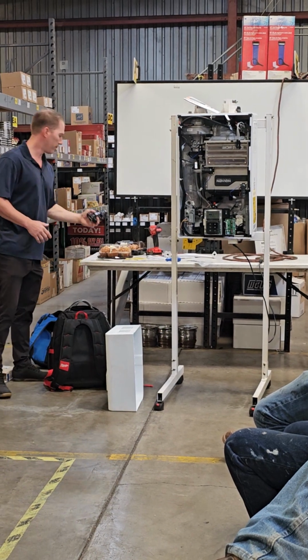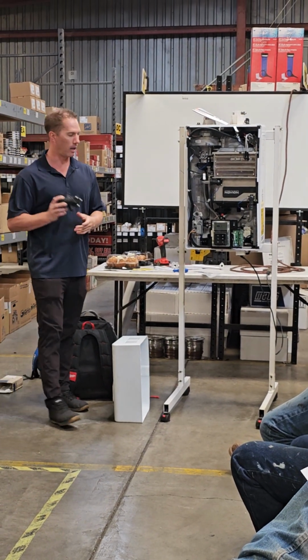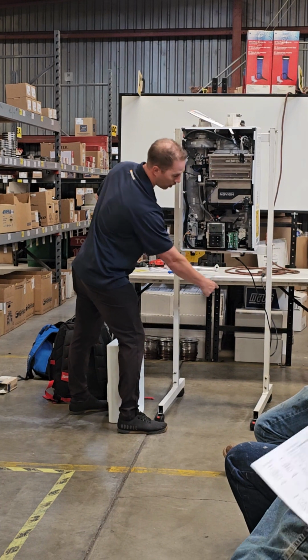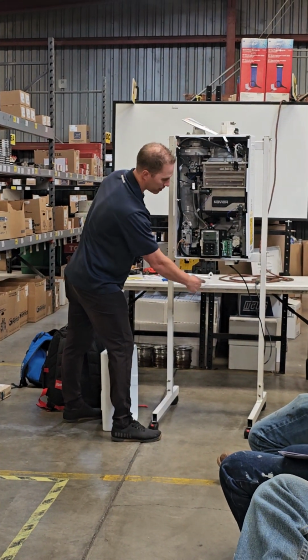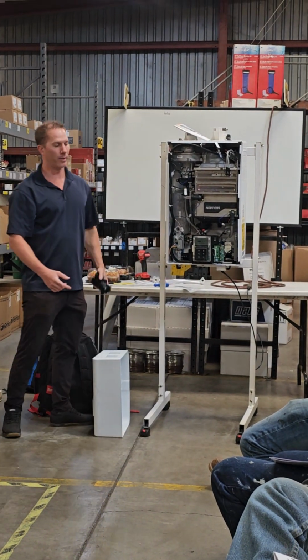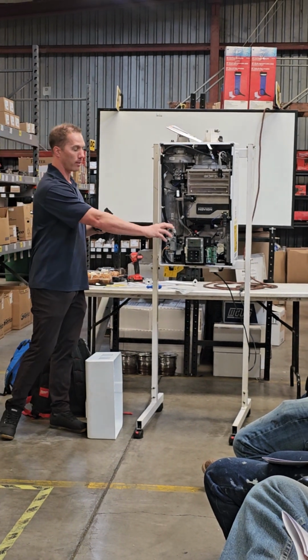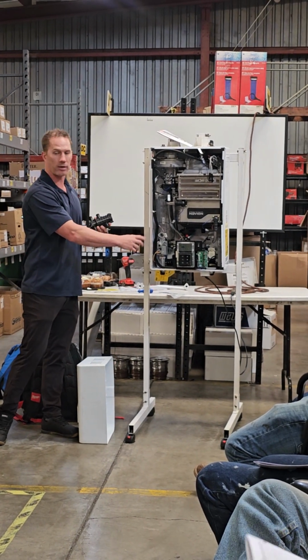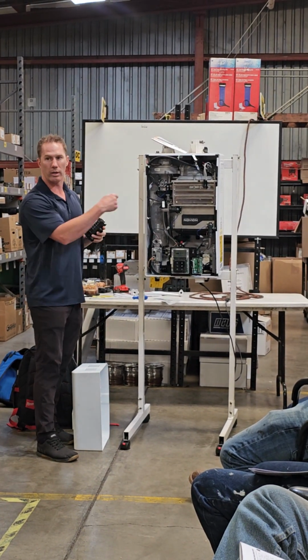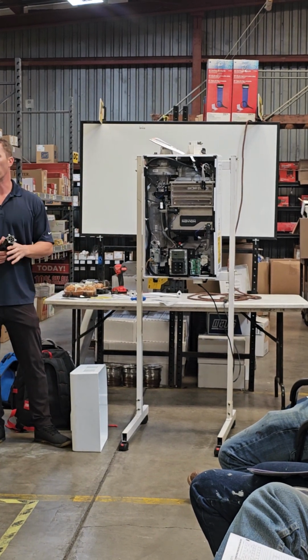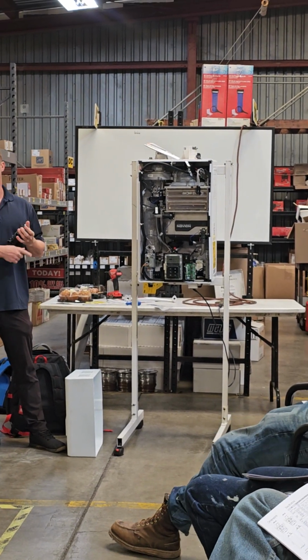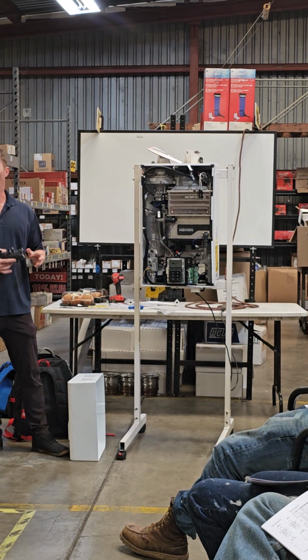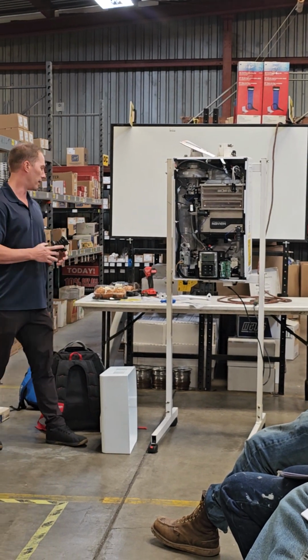With this unit, you used to have to tee over to the recirc line and put a check valve in right here. Now they changed the waterway and moved a couple check valves, so now you just do cold water in, hot water out. That's it. You don't have to do any additional piping, tee it over, or put in a check valve.